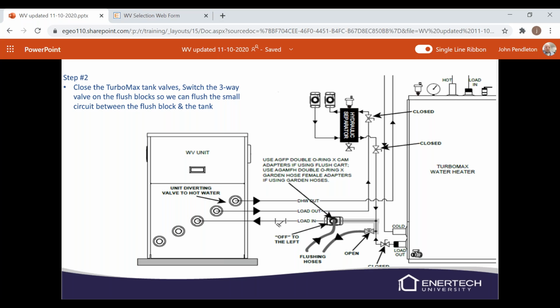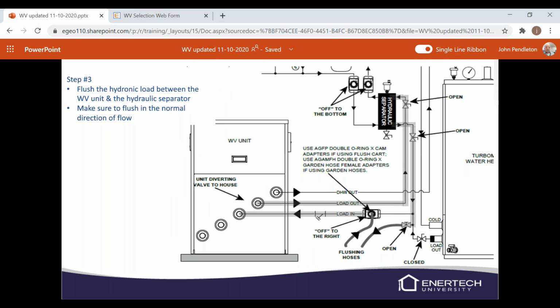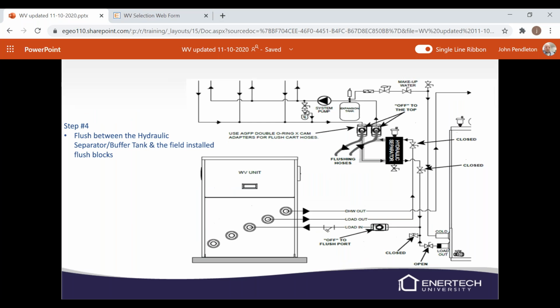Next, we're going to close off the tank, and we're going to hook into the boiler drain that's down there. There's a small little circuit in between your flush block on your load and the tank. There's a little bitty circuit there we're going to need to flush, so we'll flush that out real quick. Next, we will flush between the buffer tank or your hydraulic separator, whichever one you have, and the unit. And again, remember to flush in the normal direction of flow.